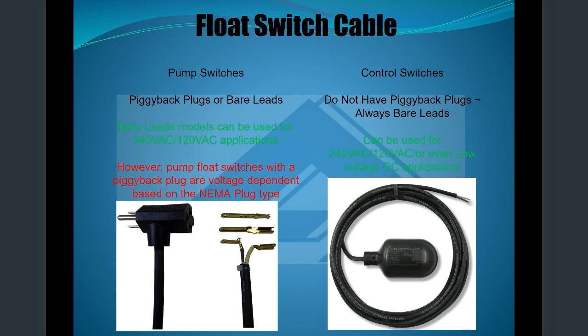All right, this kind of shows the internal mechanisms of the piggyback float. So if you're ever doing a continuity test to check a piggyback float, you'd always put your probe in the back port nearest the cable and in the front prong nearest the cable, because the electricity would flow down into the float and come back up and out. And then the ground just goes straight through, and so does the common neutral wire.